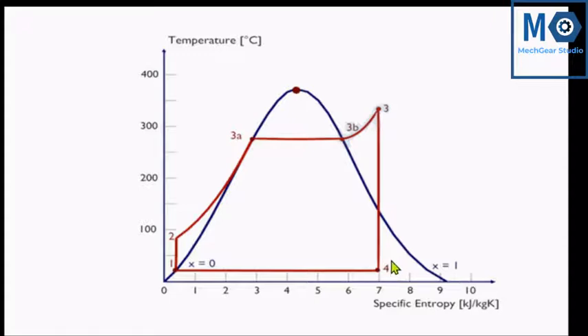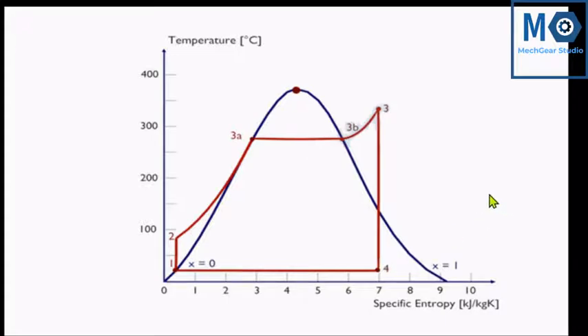So if this is a condensing type turbine, then pressure is less than atmospheric. If it is a back-pressure or exhaust type turbine, then steam is discharged at some higher pressure — slightly more than atmospheric pressure. This exhaust steam is used for some process industry and the heat of this turbine is utilized. In this case, condensation does not take place. We have to keep in mind that the exhaust pressure may be variable, depending on whether it is an exhaust type turbine or a condensing type turbine.